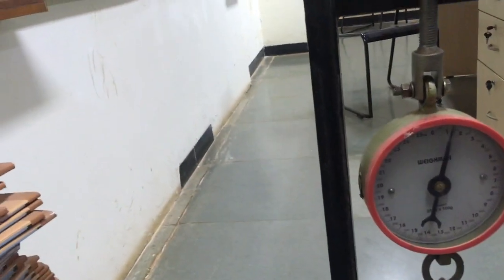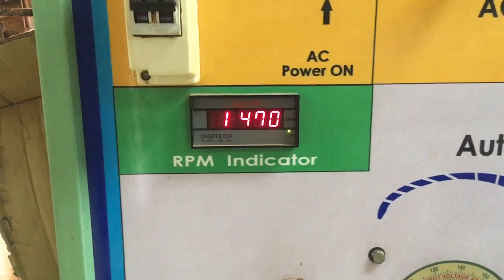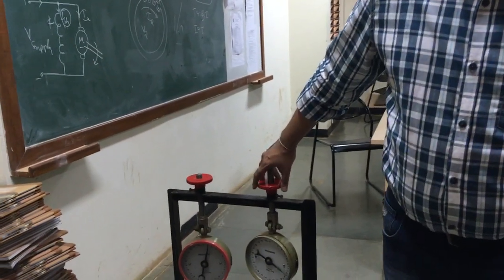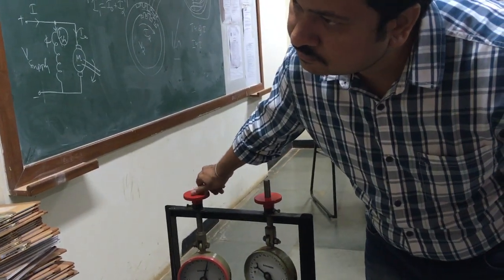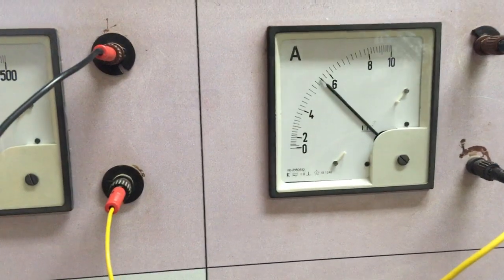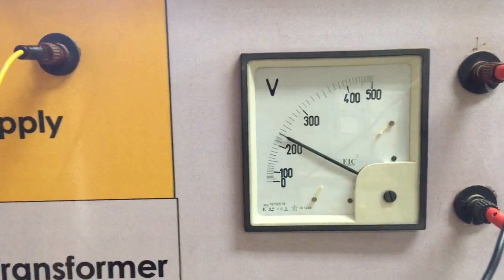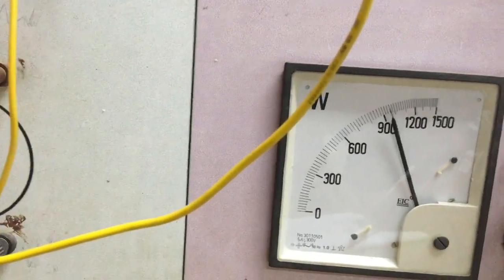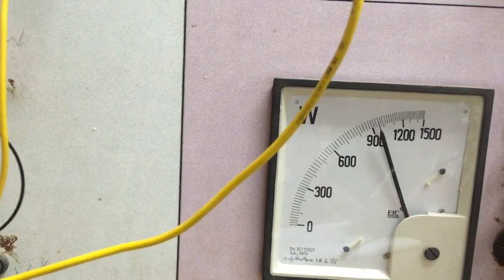F1, F2 are 7.8 and 1.2. Speed is 1470 rpm. On the third reading, I will increase it up to 5.6. Line current is 5.6. Input voltage 230. Power is 940 watts. Speed 1464. F1, F2 are 8.9 and 1.5.